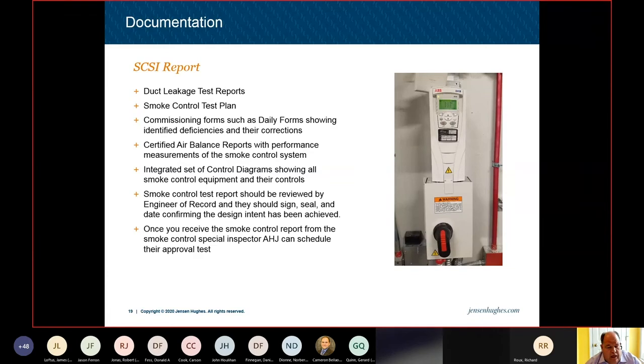And then you've got to do all that testing to make sure that holistic approach and everything works: the inputs and outputs are working properly, and the intended sequences are working properly for the smoke control. The performance measurements, whether it's CFM or pressure differentials or all the various metrics on the mechanical side for the performance, are vitally important to make all that occur.